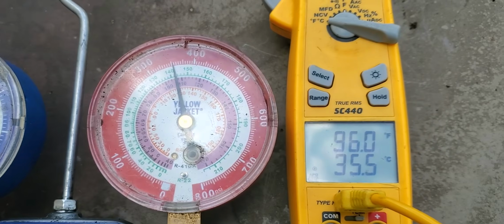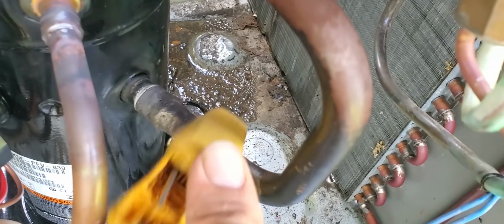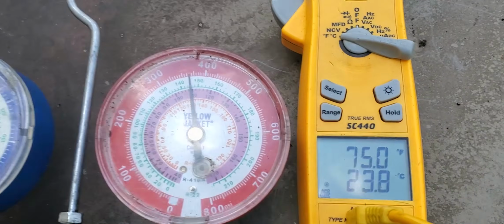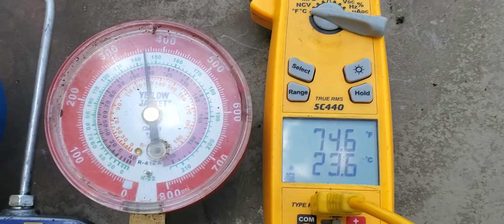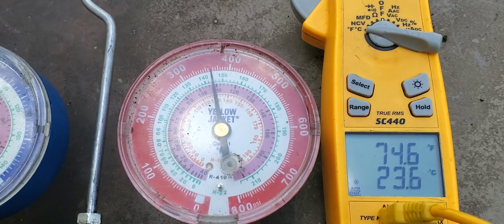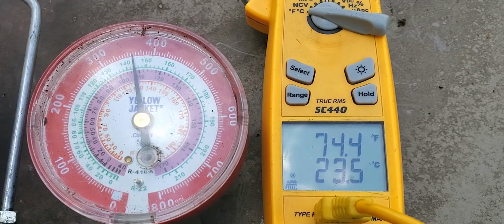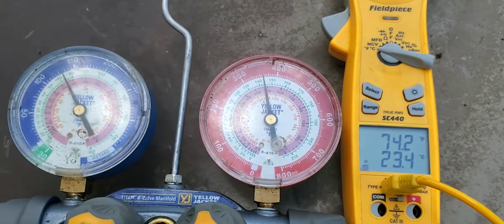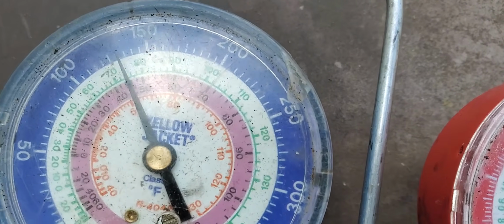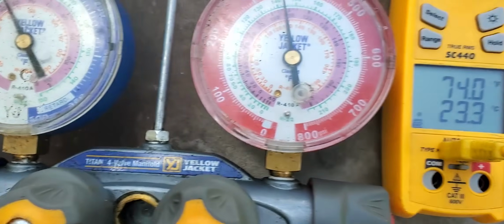A little bit more knowledge on 410A. 410A has operating pressures that are 40 to 70% higher than R22 systems and often requires a new compressor with thicker walls which can handle the higher system pressures. In addition, R410A systems require thicker ACR tubing and a condenser rated for use with R410A. R410A must use POE lubricant, and a single oil change to POE will still leave a significant amount of residual mineral oil in the system.